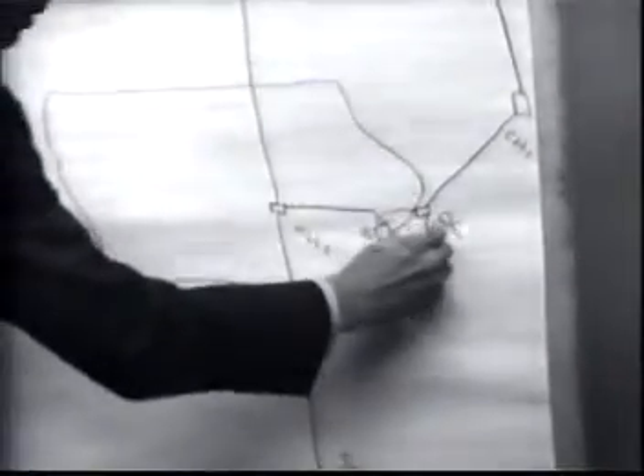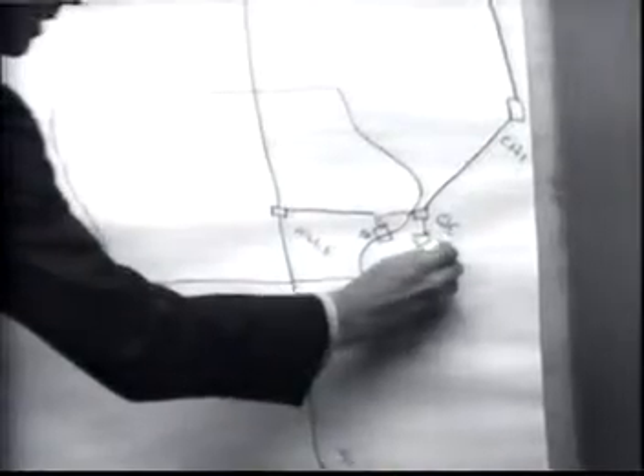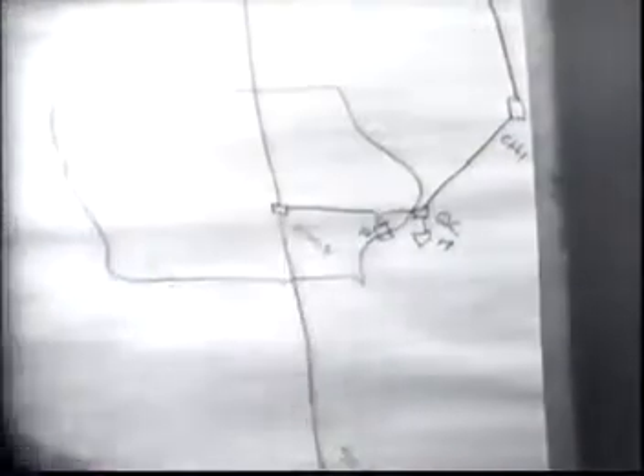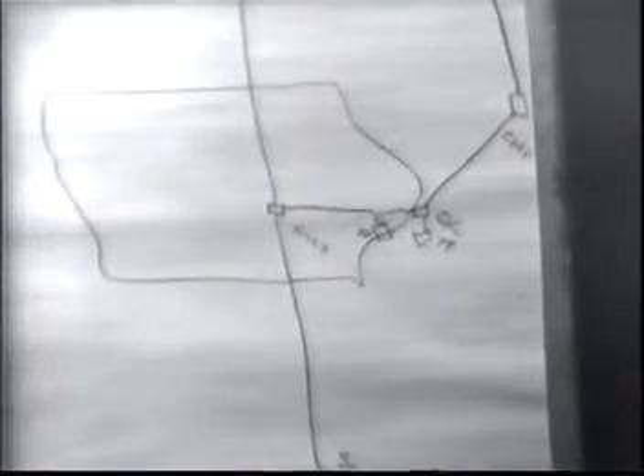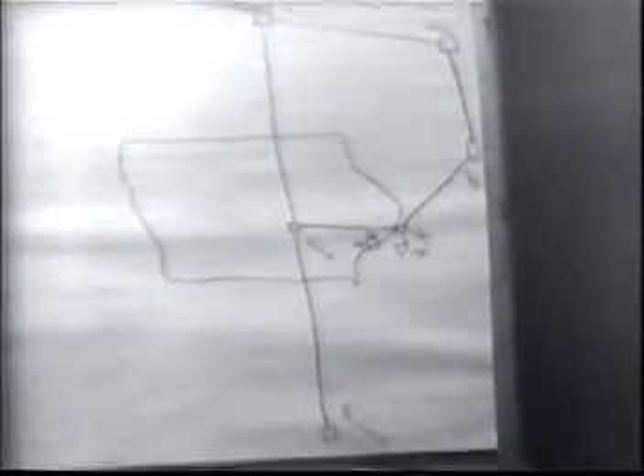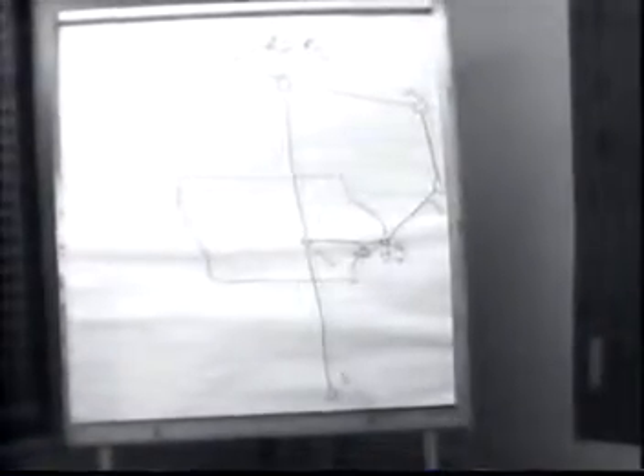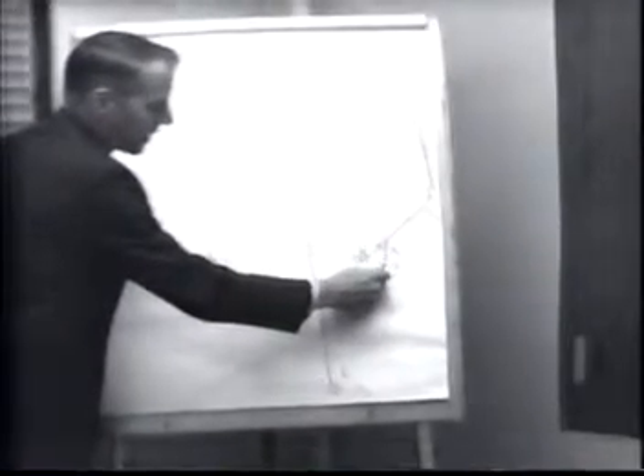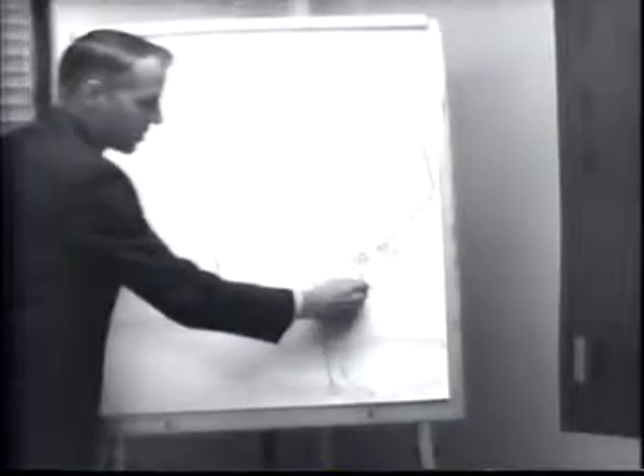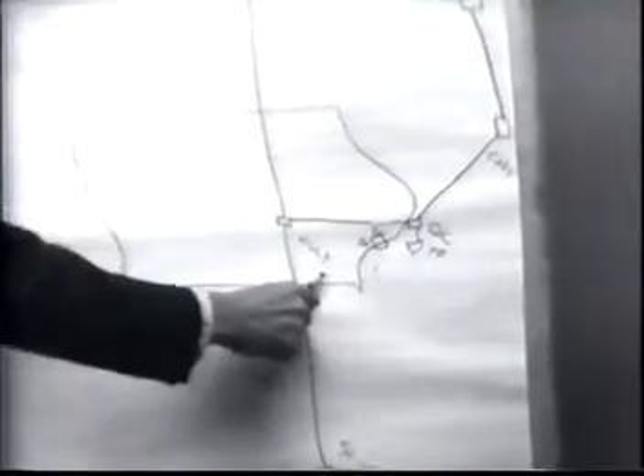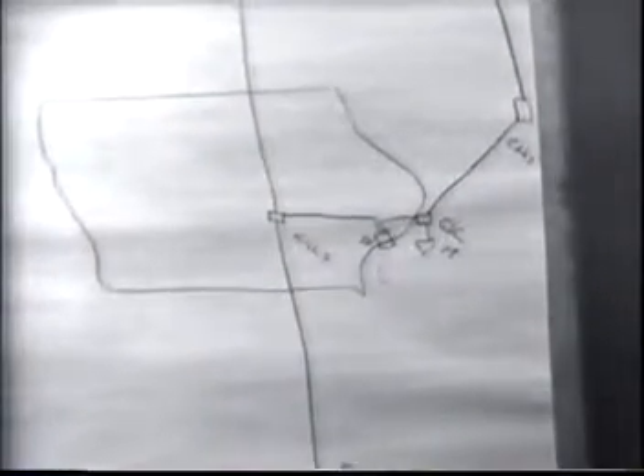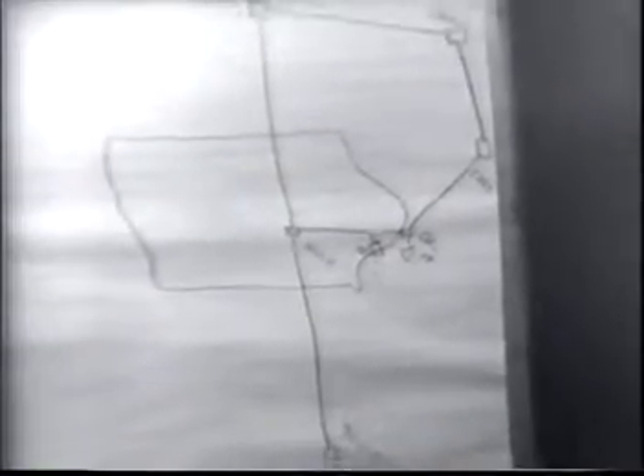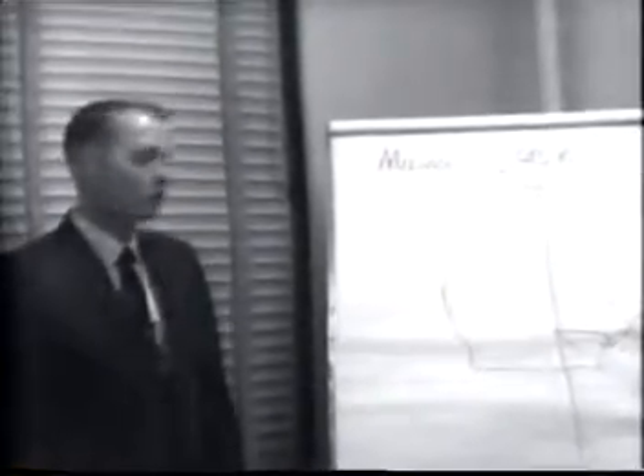From the Quad Cities, we come down here to sub 39. And at each of these points here, we have a step-down transformer from 345,000 to 161,000 volts. You can easily see the development of the next stage of our transmission system, a loop from sub 39, extending in some manner basically around to sub 56, or to another plant downriver and then back to Hills. There are several possibilities for expansion of the loop system then. There again, with the aim of providing greater reliability to the major load centers from a dual feed.